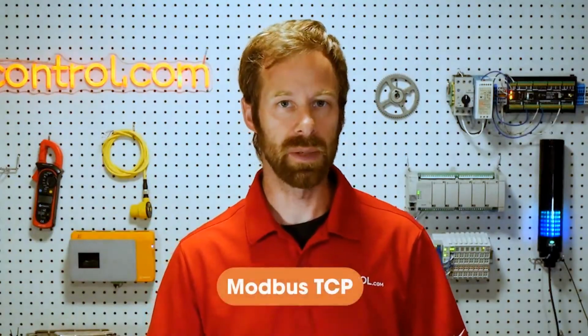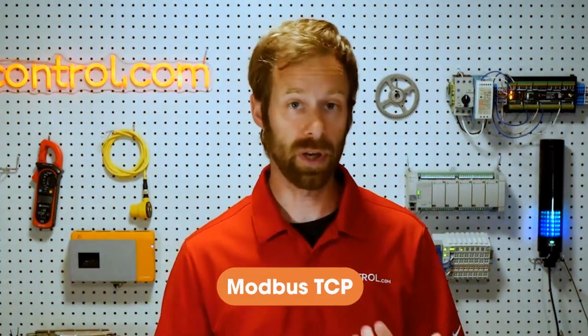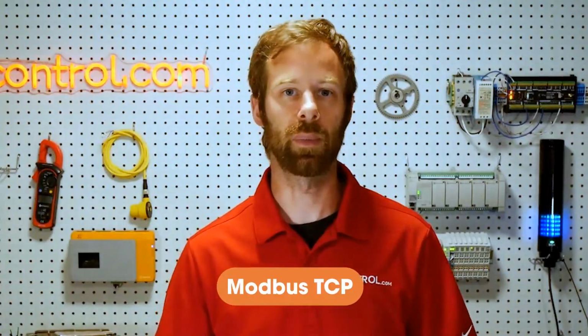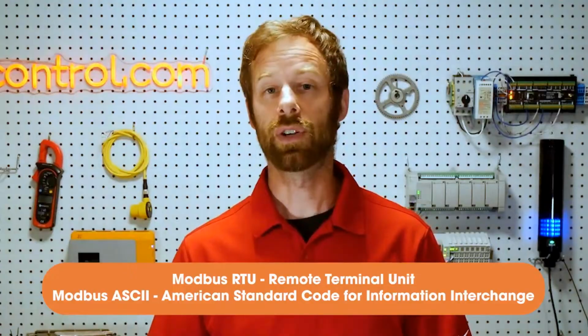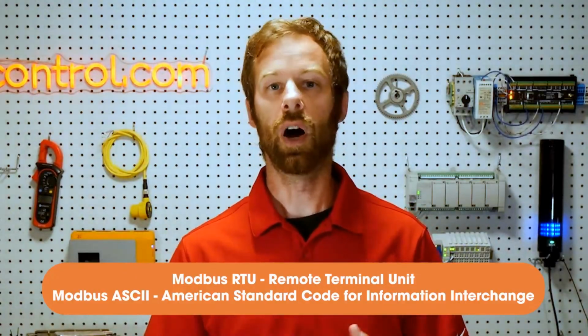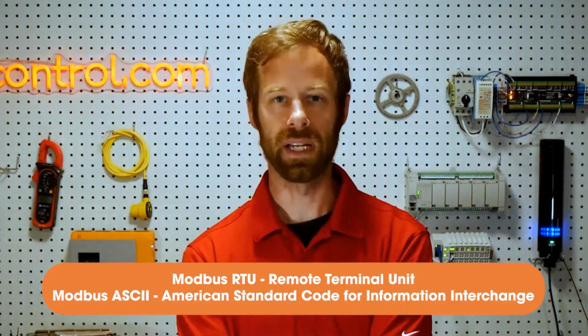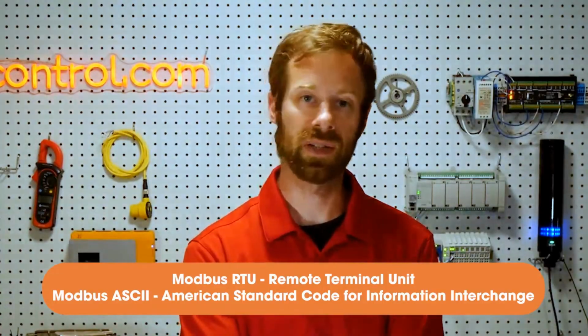So we send a command and an address, and those are packaged into another kind of device protocol, a carrier, if you will. Now, these carriers, most commonly that we see today, are Modbus TCP, which is a variation of the transmission control protocol, much like Ethernet, so they look a lot like an Ethernet port. But we also have Modbus RTU and ASCII, which are very commonly transmitted over RS-232 and RS-485 connections, RS-232 being a serial connection, RS-485 being a twisted pair multi-drop kind of connection.